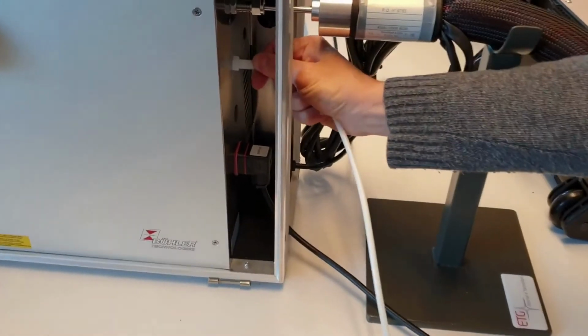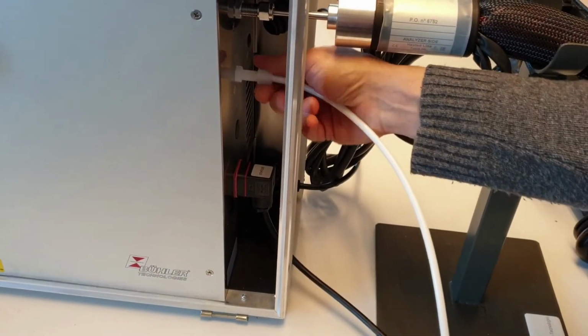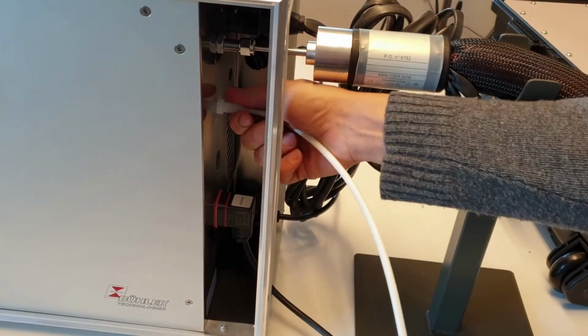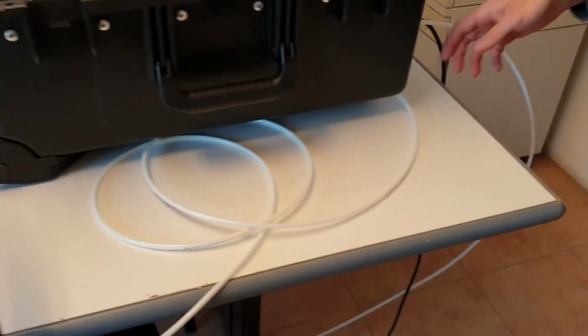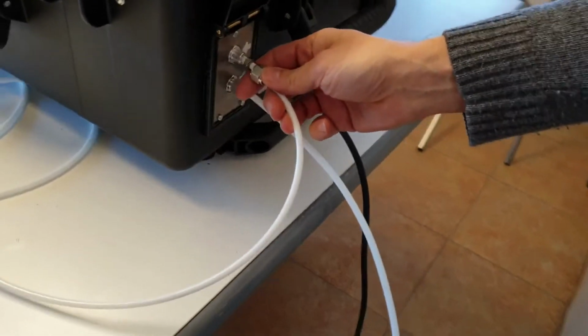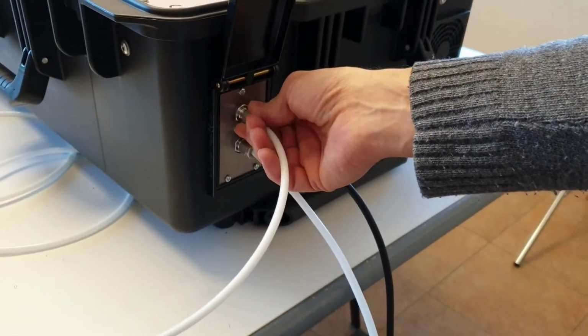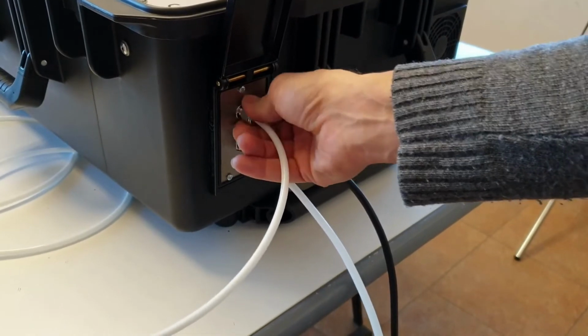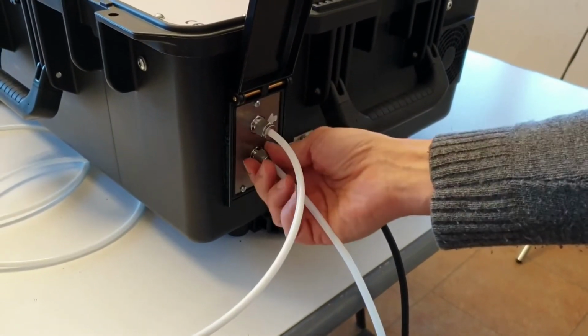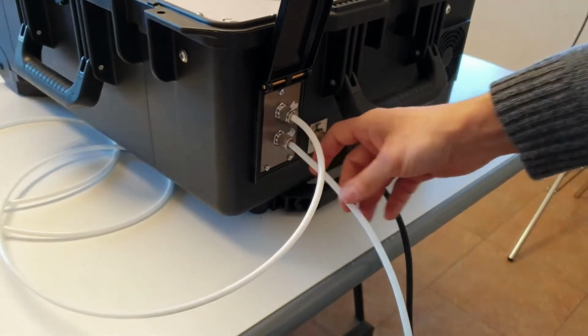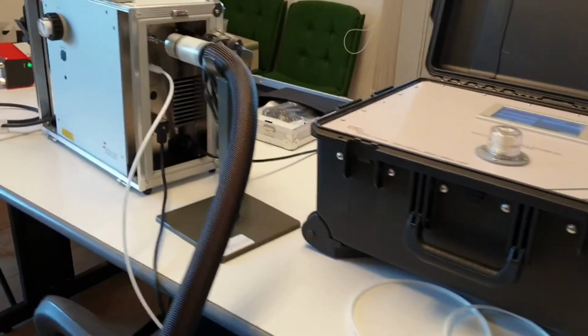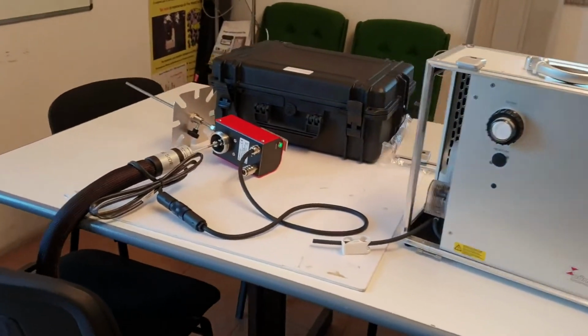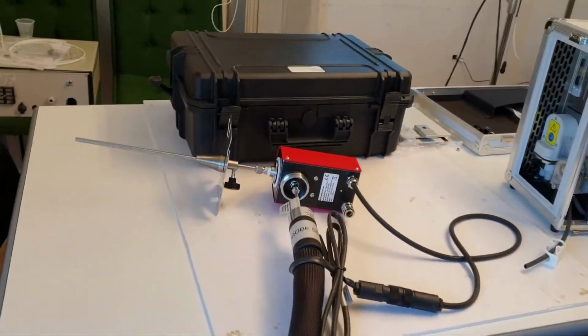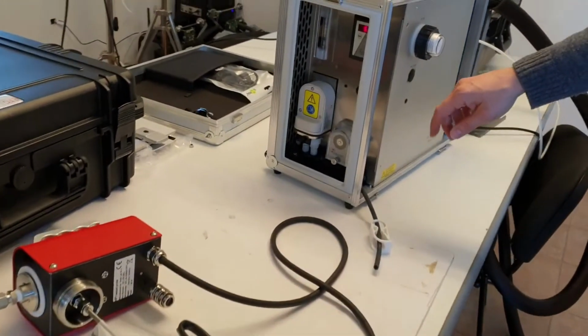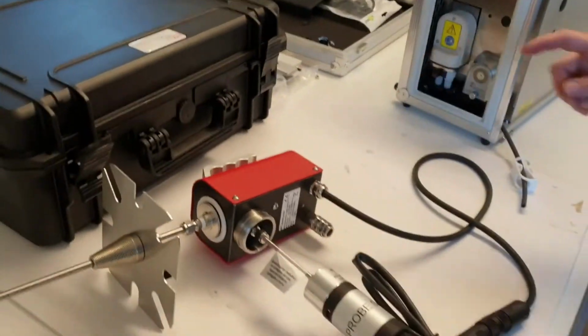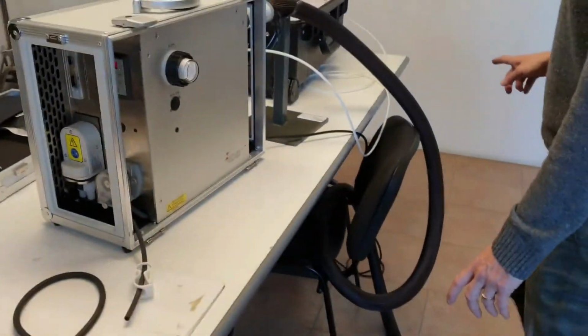We can connect pneumatically the sample out of the conditioning unit to the sample in of the analyzer. Connect also the exhaust gas. And now the sampling goes from the probe to the analyzer.